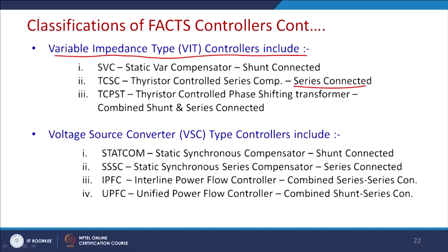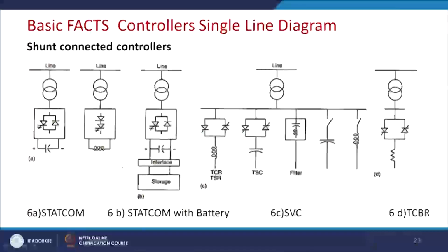Similarly, the thyristor controlled phase shifting transformer is used as a PAR, power angle regulator. Other types of FACTS devices are voltage source converters. These are STATCOM, which is shunt connected, and SSSC, which stands for static synchronous series compensator. Thereafter you have the interline power flow controller, which is a combined series combination, and thereafter you have UPFC, the unified power flow controller, or UPQC, the unified power quality conditioner. For power quality we say power quality conditioner, and for FACTS we say power flow controller. Now these are the pictorial representations of the different acronyms which I have just explained.